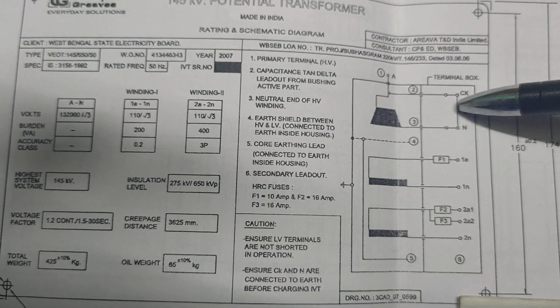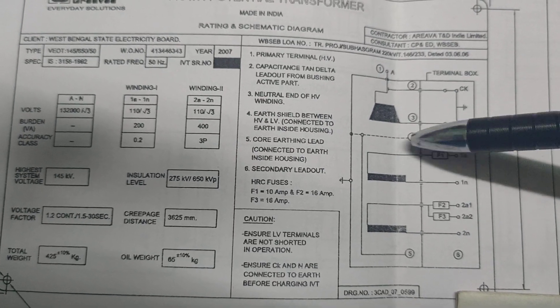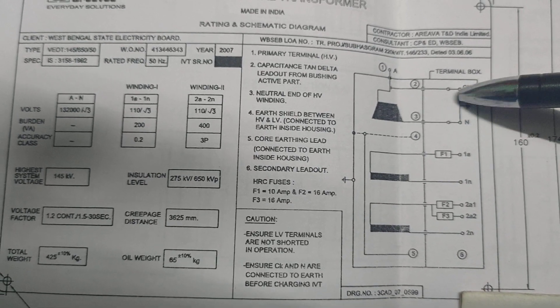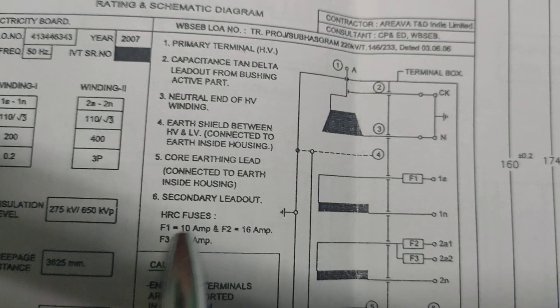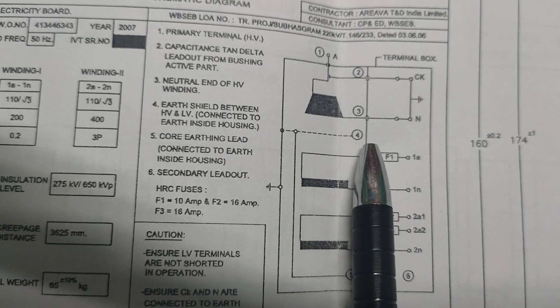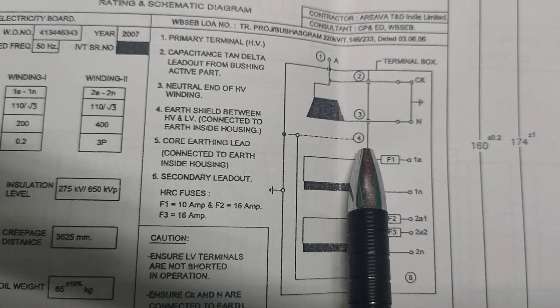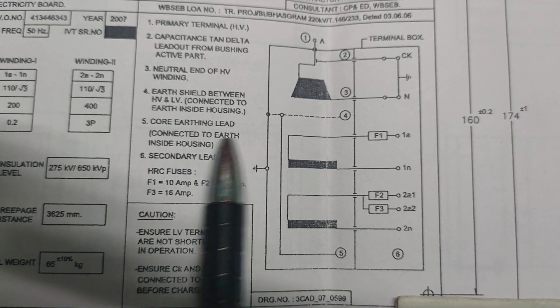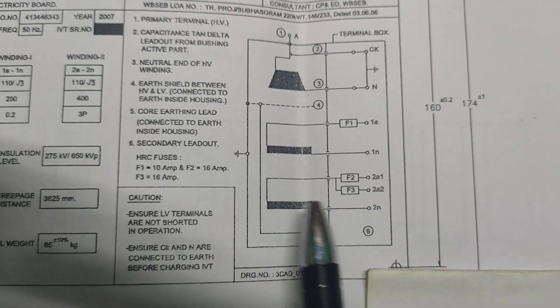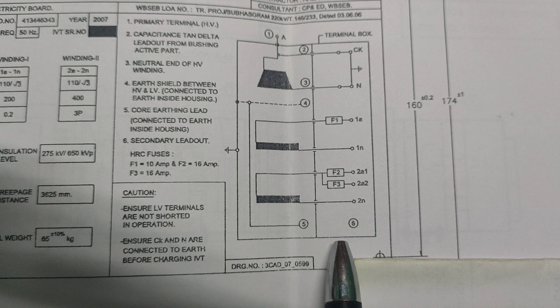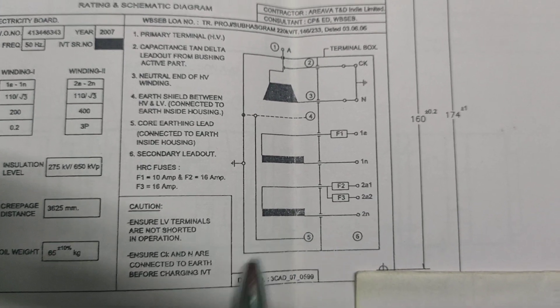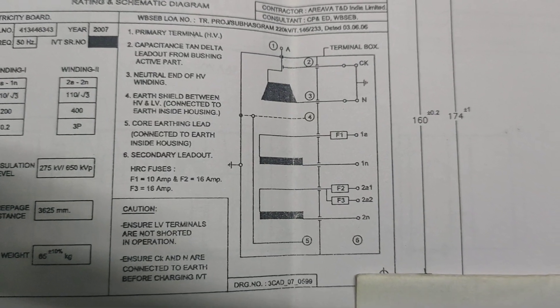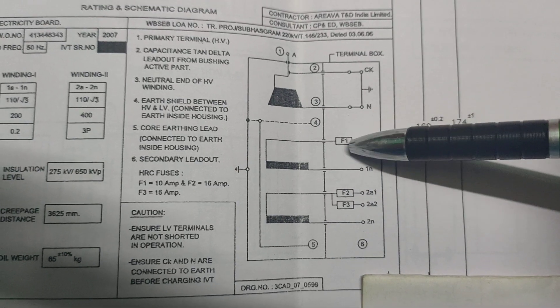The 3 is the neutral link. Neutral and Ck point should be shorted and earthed properly. Number 4 is the earthing shield between HV and LV connected to the earth inside housing. 5 is the core earthing lead connected to the earth inside housing.